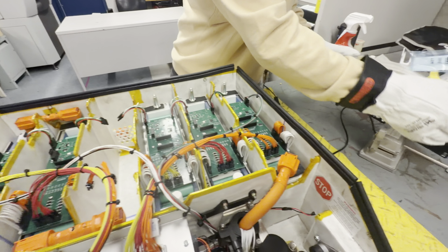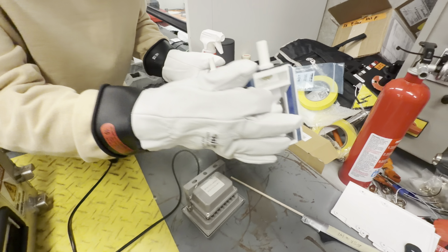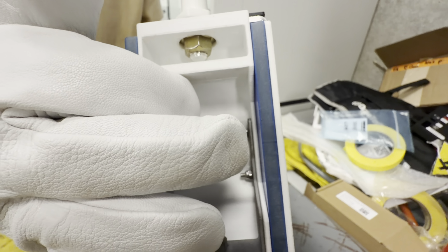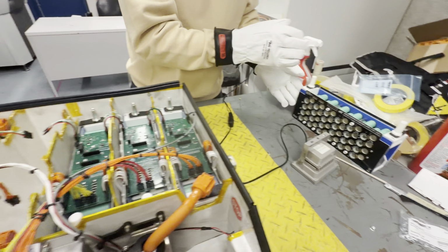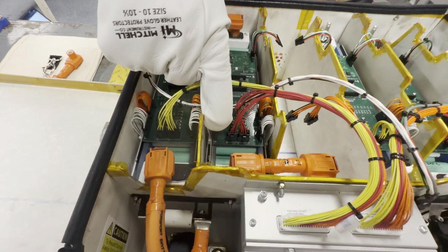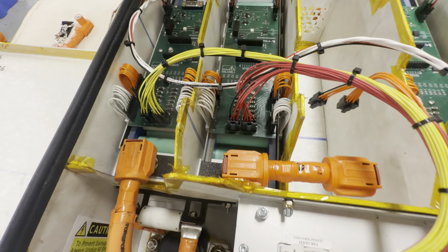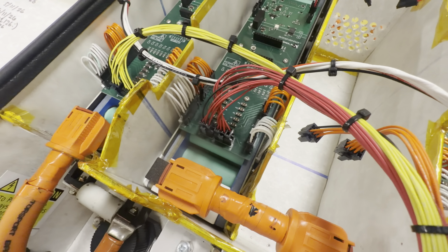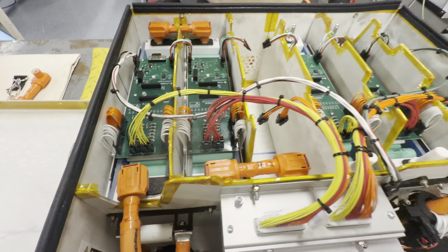I'd also like to show how our subpacks have positive locking for all the maintenance plugs using prevailing torque nuts. All of the RADLOK service connections are insulated. You can see they have covers on them, and they can only be connected at the connector contact point.